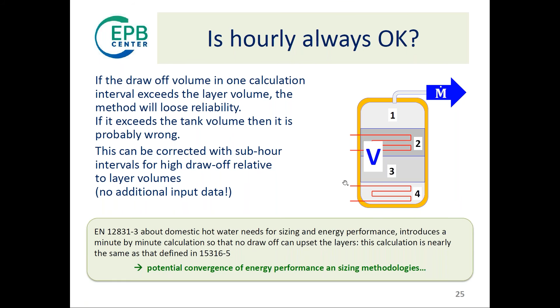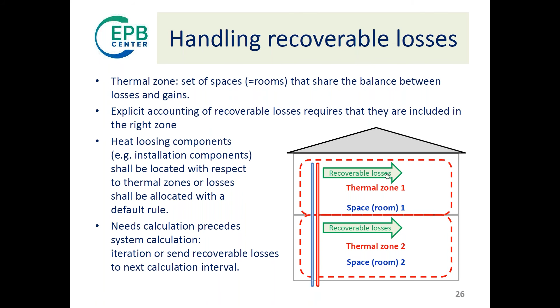Another feature, which is more and more important, and general for the whole package, also applies to heating systems: if you insulate your building, it becomes more important to take into account recoverable losses inside your calculation of needs. If you have components that may lose heat, you need to attribute the recoverable losses to the right thermal zone. Remember, the thermal zone is a set of spaces that share the balance of losses and gains. It's important to attribute to the right one, because if it's very well insulated, even low losses can significantly influence the balance of your thermal loss.